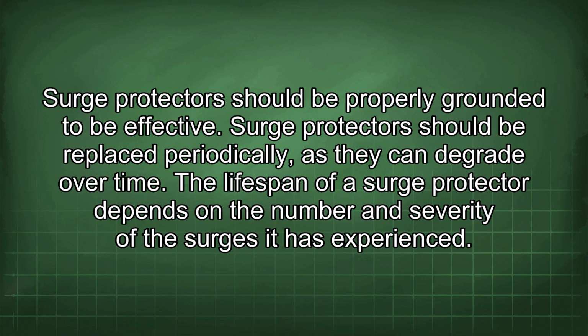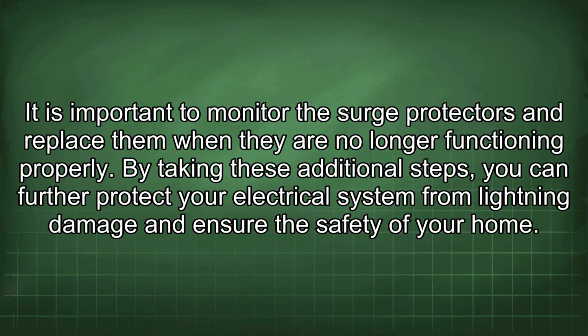Surge protectors should be replaced periodically as they can degrade over time. The lifespan of a surge protector depends on the number and severity of the surges it has experienced. It is important to monitor the surge protectors and replace them when they are no longer functioning properly. By taking these additional steps, you can further protect your electrical system from lightning damage and ensure the safety of your home.